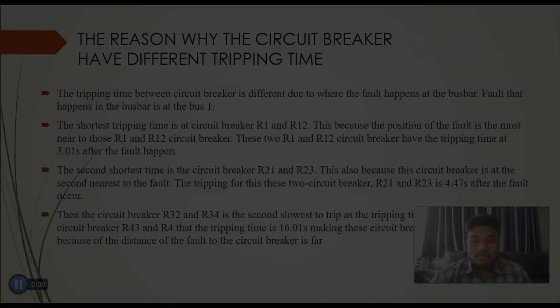Alright, so we need to understand that a different position of the fault will give a different result. And for this situation, it happened at bus bar 1, as we can see at the circuit above. The circuit breakers R1 and R12 have the shortest tripping time. This is because the location of the fault is closer to R1 and R12. And the tripping time for these two circuit breakers is 3.01 second after the fault occurs.